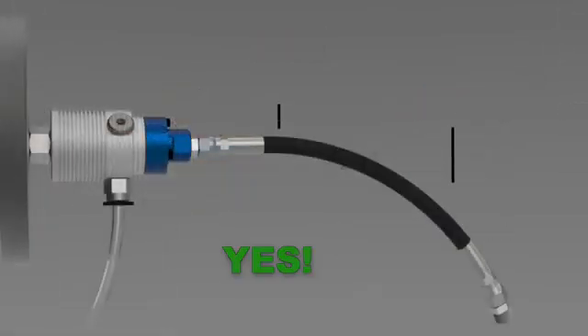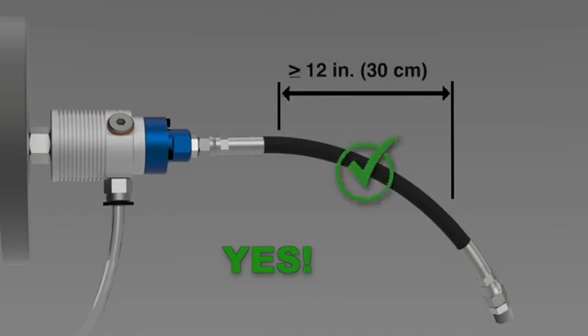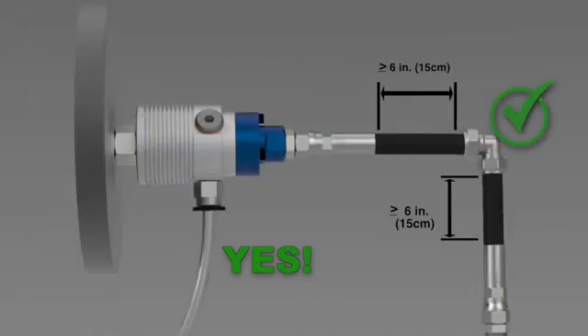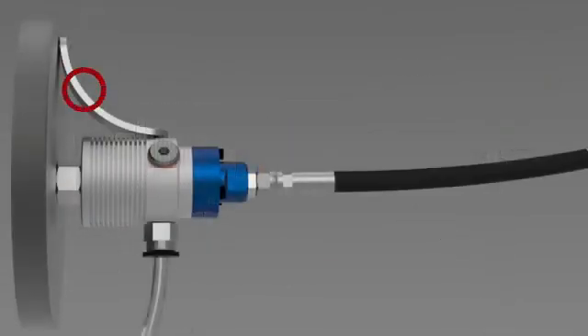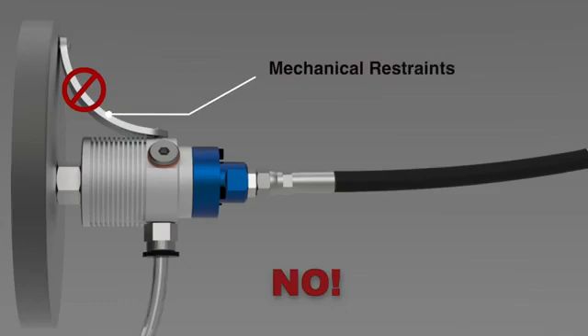Side loads are minimized when the supply hose has sufficient length and only slight bends. An elbow can relieve stress from tight bends in the supply hose. Mechanical restraints of any kind also create side loads on the union and are not recommended. Avoiding side loads from hoses or mechanical restraints will prolong the life of the union's bearings and seals.